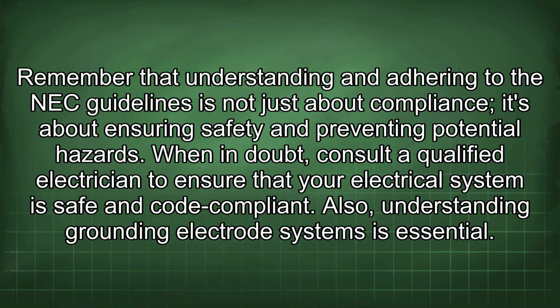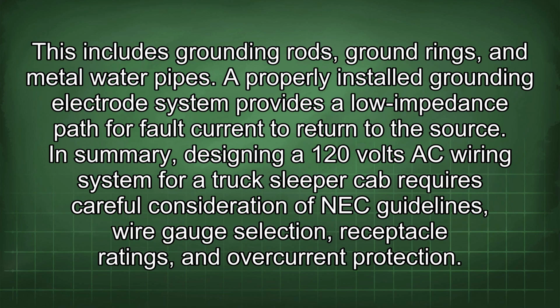Remember that understanding and adhering to the NEC guidelines is not just about compliance, it's about ensuring safety and preventing potential hazards. When in doubt, consult a qualified electrician to ensure that your electrical system is safe and code compliant. Also, understanding grounding electrode systems is essential. This includes grounding rods, ground rings, and metal water pipes. A properly installed grounding electrode system provides a low impedance path for fault current to return to the source.